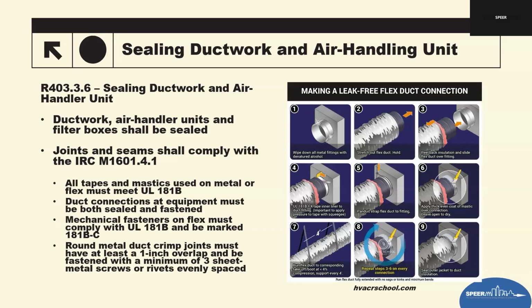This prevents joints from separating under pressure when the ducts get pulled, or if they're hanging and starting to pull on the collar. If there's just two on the top and the duct is being pulled up, the bottom will come loose. So most duct leakage failures start at improperly sealed or fastened joints. So using the correct UL listed material and proper mechanical fastening is the foundation for passing duct leakage testing.